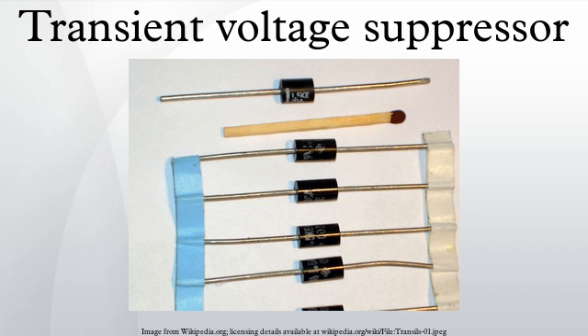For example, MOVs have been documented to have frequently caused fires when exposed to over-voltage sufficient to activate the MOV and start conducting, but not enough to totally destroy it or blow a house fuse. That condition caused significant heating of the MOV, which in turn caused the printed circuit board and MOV to burn, eventually starting a fire.